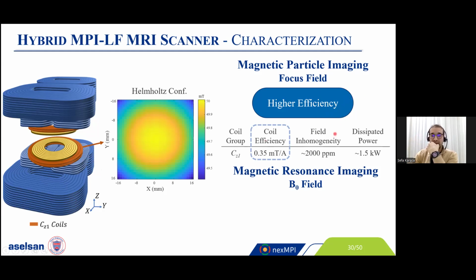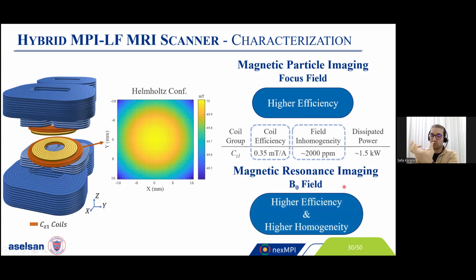But this is a bit problematic in the case of MRI, because for the B0 field, having higher efficiency is still great, but we also require higher homogeneity. In our case, our field inhomogeneity is 2000 ppm, which is quite a lot for MRI. In conventional MRI scanners, the field inhomogeneity is in the range of a few ppm. But the good thing about low-field MRI is that it is a bit less sensitive to field inhomogeneity, but still we have lots of trouble because of it. I'm going to show the results in the simulation and the experimental studies. We have lots of artifacts because of this field inhomogeneity. So there is a certain trade-off between the MPI and MRI design criteria, even though in both of them we just generate a homogeneous magnetic field.